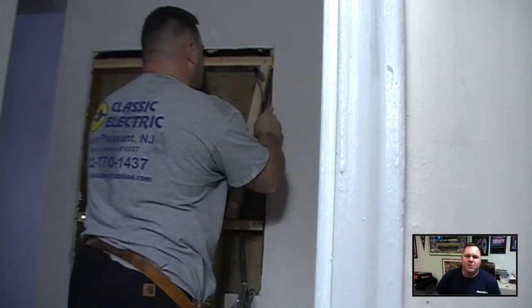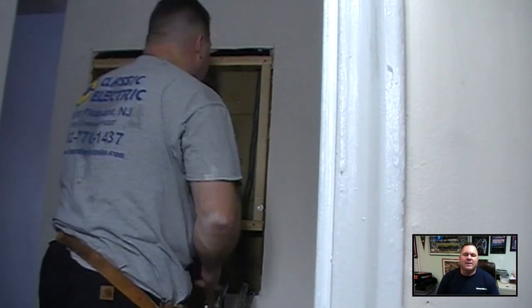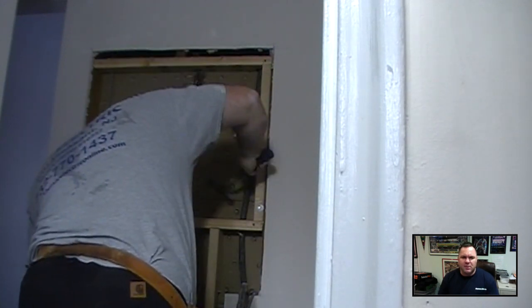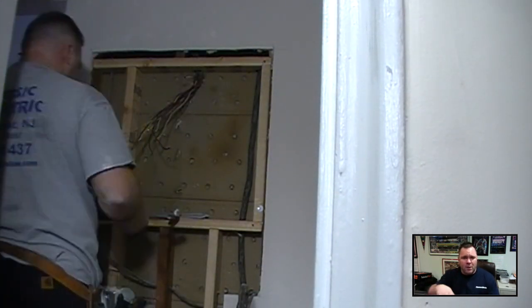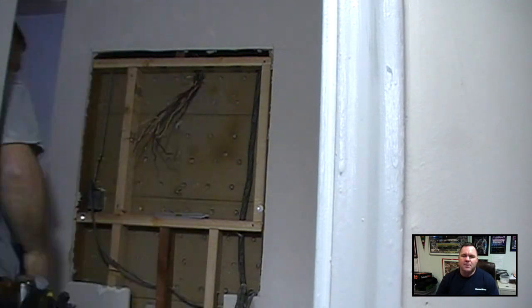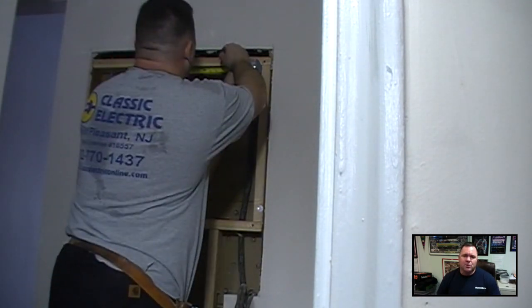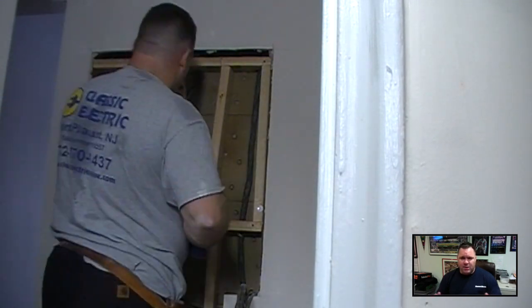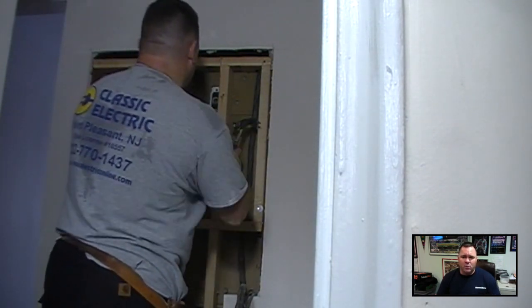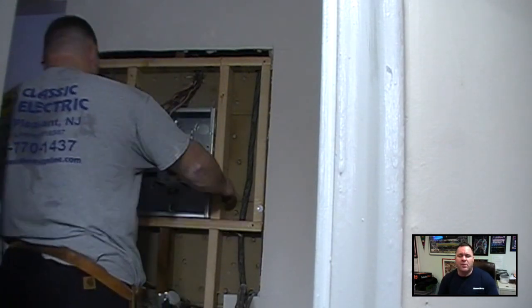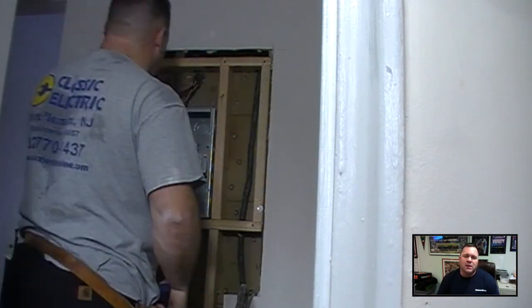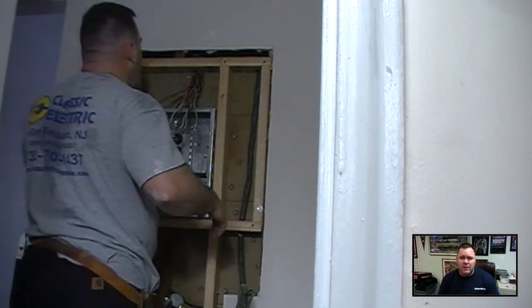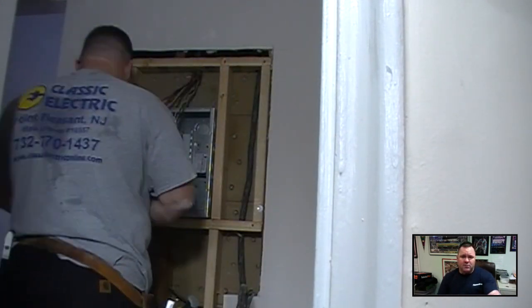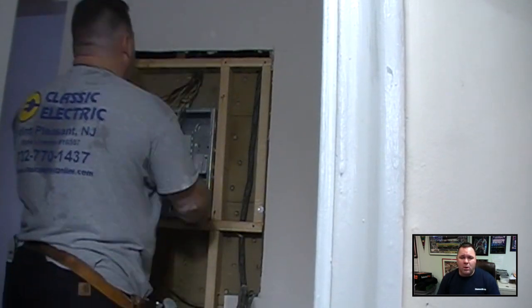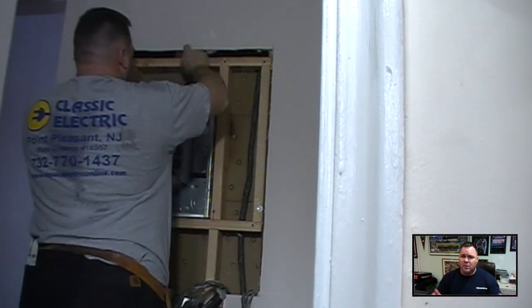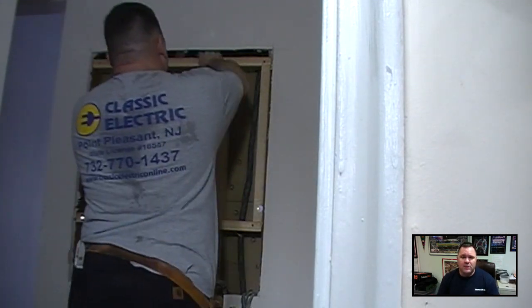As you can see in the video, once I got started, I realized there was a feeder coming from the basement going up to the second floor above where I'm working. I wasn't going to be able to fit the enclosure in the space between the stud bay because of that cable in the way, shown on the far right in the framing. So I had to run out and get some lumber and frame a wall, putting in a header to pick up that load from the stud, to make room for the new electrical panel.